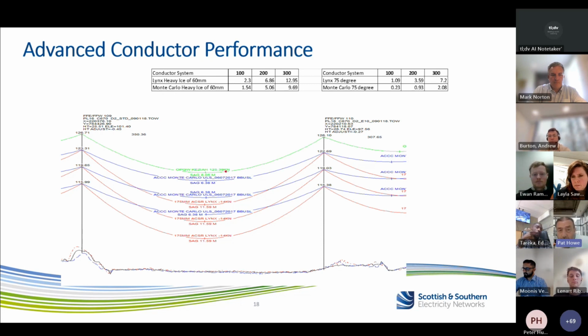One of the things you'll see on the next slide is that the new low sag conductor is so good that the earth wire would have been dropped below the top conductor. Such is the benefit in increased ground clearance, so if you have an earth wire, you'll probably need to change that at the same time. We took the opportunity to change it for one containing fibre, so we got better comms and better protection and control out of this as well.